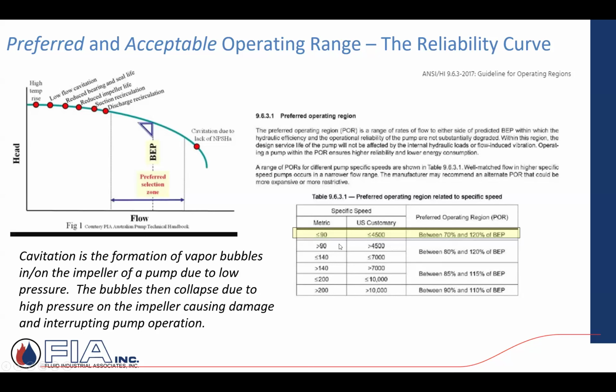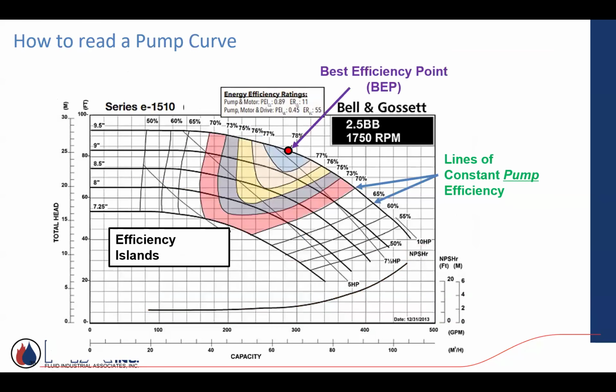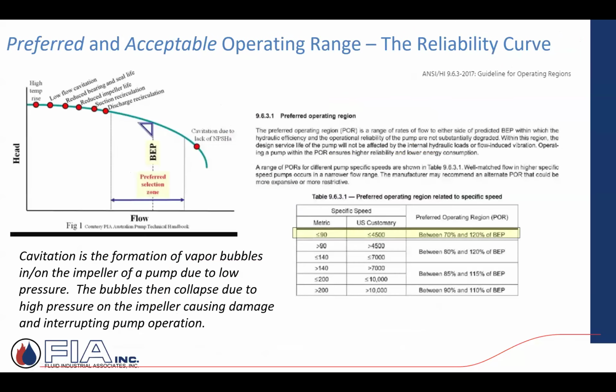And again, there are all these different ratings that come from the Hydraulics Institute. We're dealing with speed, so less than 4,500 RPMs. That's our world. 3,600, 1,800, 1,200 RPMs. So typically, we don't want to exceed 70% to 120% of BEP. So 20% greater, 30% less of that BEP. Now, what were we looking at right here? In this particular pump, this is the BEP. So if I go 30% to the left, 20% to the right, I'm within Hydraulic Institute, ASHRAE, all these other governing bodies. That's okay. Pump manufacturers say, yeah, the pump's going to operate. It's not going to create problems. You start drifting outside that, you're going to have some issues with the life and the performance of that pump that you've specified.